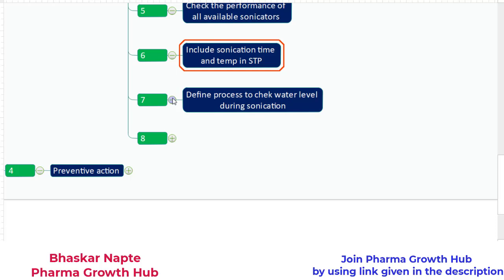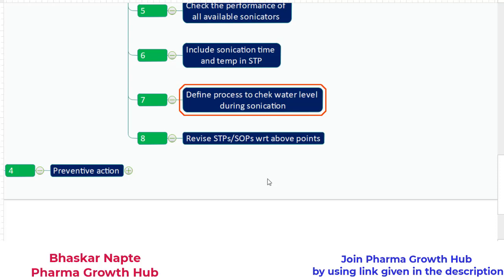The seventh point: define a process to check the water level during sonication. Even if the sonicator is running, if the water level is not up to the mark, sonication will not happen effectively, which will hamper your extraction and assay. Define this process in your SOP for the sonicator. Finally, revise all standard test procedures and standard operating procedures with respect to the above applicable points. If you find additional points that need to be investigated as part of corrective action, please do that as well.